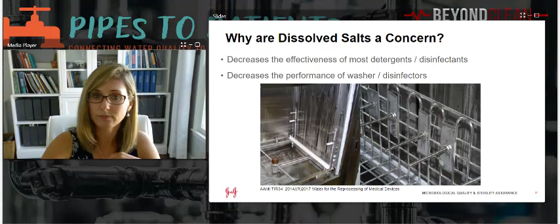In addition, hard water is not good for washer disinfectors; they really don't like it. Hard water deposits can foul up the electrical heating elements or heat exchanger components needed for heat transfer efficiency, which can mean your washer disinfector isn't cleaning the way it's intended to, which is really problematic when you're relying on that for the processing steps prior to terminal sterilization or disinfection.